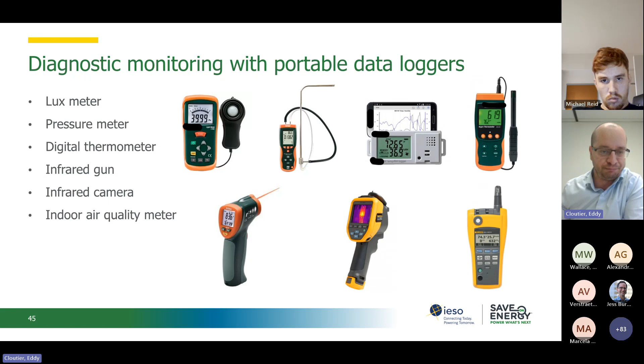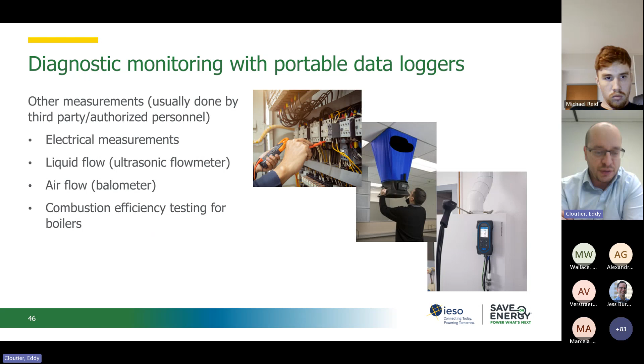And finally, you might need other measurements that will usually be done by a third party, or in some cases, the building manager or building operating team also have these types of measurements, but I would say it's not that often that you will see those conditions. So you might want to do electrical measurements with a certified electrician, liquid flow using an ultrasonic flow meter, airflow or water flow measurement with a balancing contractor, combustion efficiency testing for boilers, and so on. Usually engineers don't always have this measuring equipment. So in those cases, if needed for the existing building commissioning project, you might want to retain the services of a third-party contractor to do some measurement.